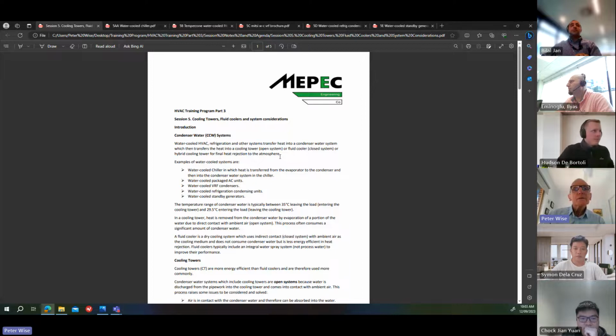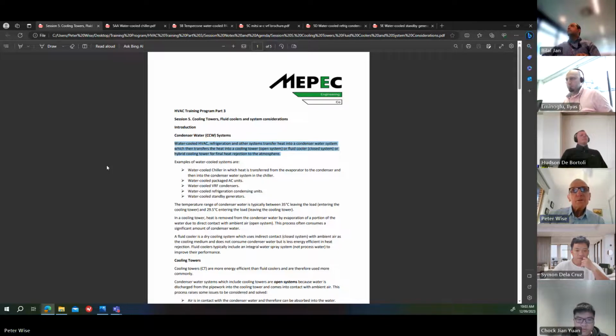Good. Okay, so we're talking about cooling towers, fluid coolers, and the considerations for those types of systems. And we're talking about condenser water systems, which we've touched on before on a few occasions. So water-cooled HVAC, refrigeration and other systems transfer heat into a condenser water system, which then transfers the heat into a cooling tower, which is an open system, or a fluid cooler, which is a closed system, or a hybrid cooling tower, which is also a closed system, and we'll talk a bit more about those as we go along. And then the heat is rejected to the atmosphere.